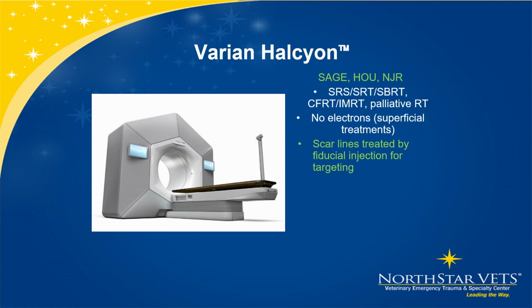The problem I have with this is that we don't have electrons. Because of the C-arm Linacs, we actually had a tungsten target we put in the way of the treating electrons, and we would get photons. If you move the target out of the way, now you can treat directly with the electrons. Electrons kind of come out in a teardrop shape, and they are superficially distributed. So scar lines after surgery, I love to use electrons for.